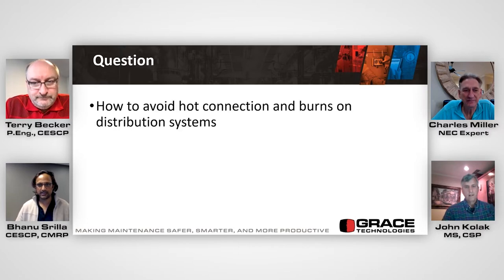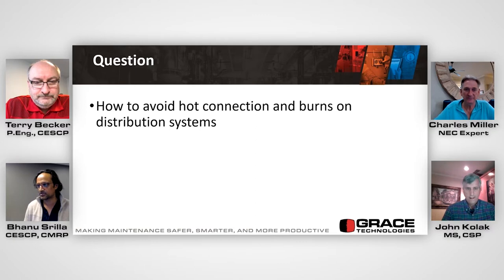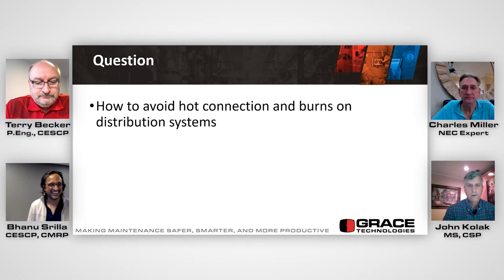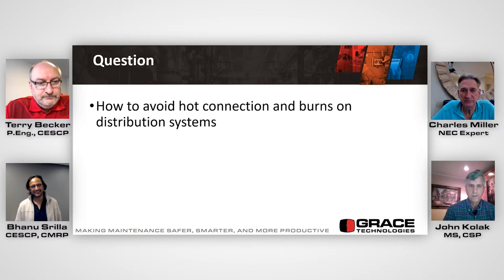So this is probably going to be John again. How do you avoid hot connections and burns on distribution systems? Clean the connections. If you want to know if somebody's properly trained, they will clean the oxidation off the conductors. They will make connections with the right type of connector. In other words, try to avoid bolted connections if you can. Squeeze-down connectors or ferrules, that's the way to go.